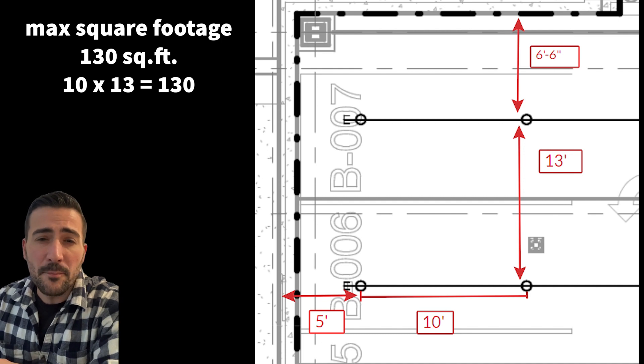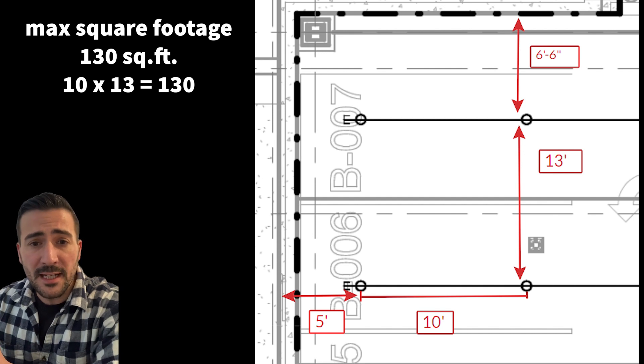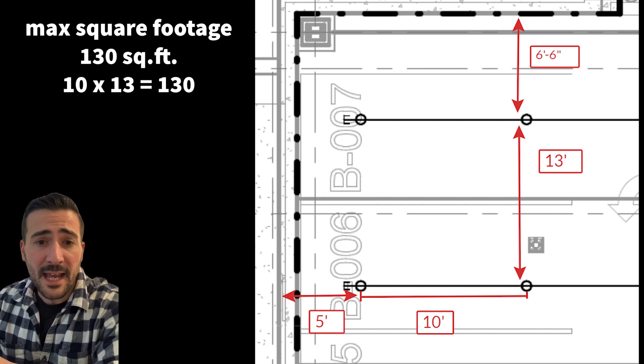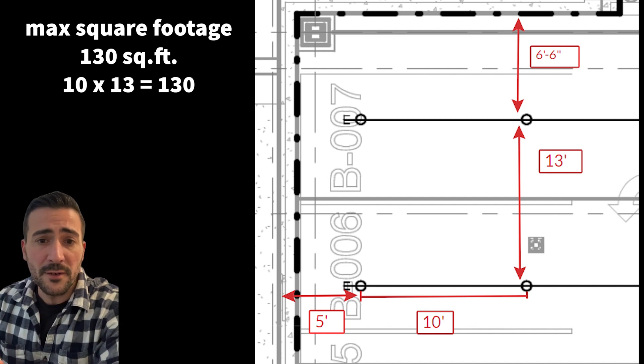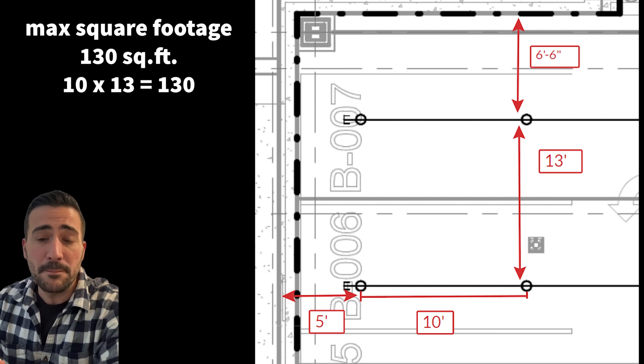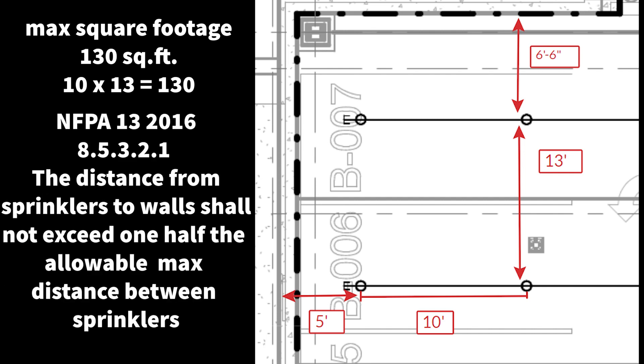Let's take a look at this example to see how max distancing on ordinary hazard works. 10 times 13 is 130, so I space these heads 10 feet by 13 feet, which is 130 square feet — and that's the maximum square footage for the standard spray upright and pendant in ordinary hazard. Then you would use NFPA 13's installation requirements: the distance from the sprinkler to the walls shall not exceed one half the allowable max distance between sprinklers.